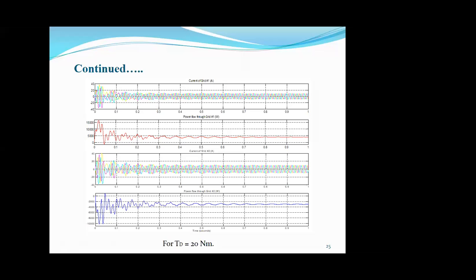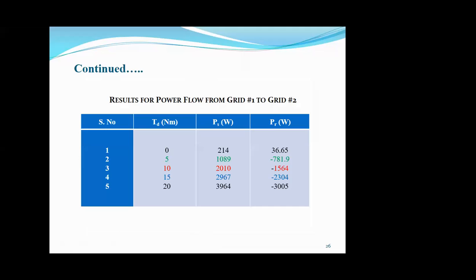So this is the tabular result which shows how power flow is varying. When torque TD was 0 Newton meters, PS was positive and PR was positive, meaning both were supplying power to the VFT to energize itself — no power flow was taking place between the grids.